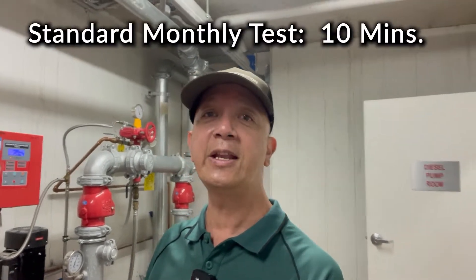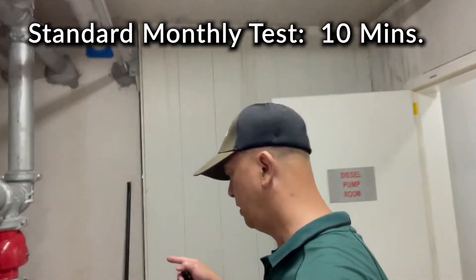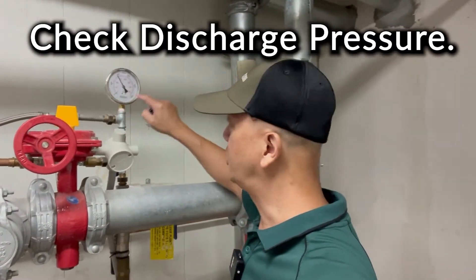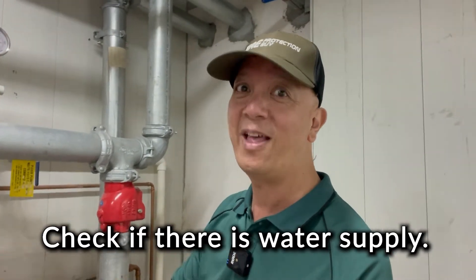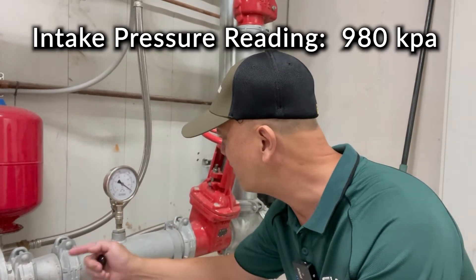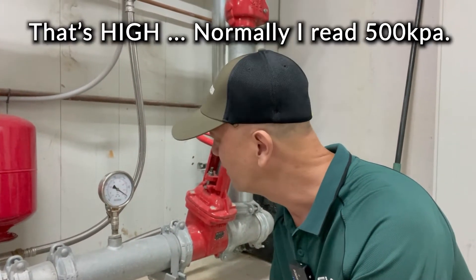We normally do the testing for 10 minutes. You also have to check the water gauges — that is the discharge — and also check if there is water in the system before you run the engine. Look at that: our town's main water supply intake is around 980 kPa. That's pretty high; normally it's only 500 kPa.